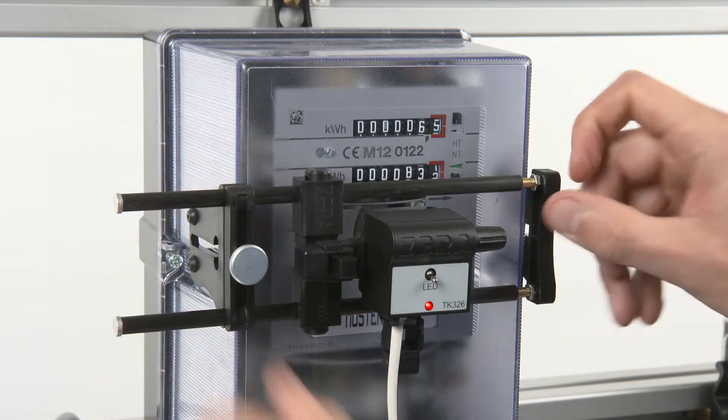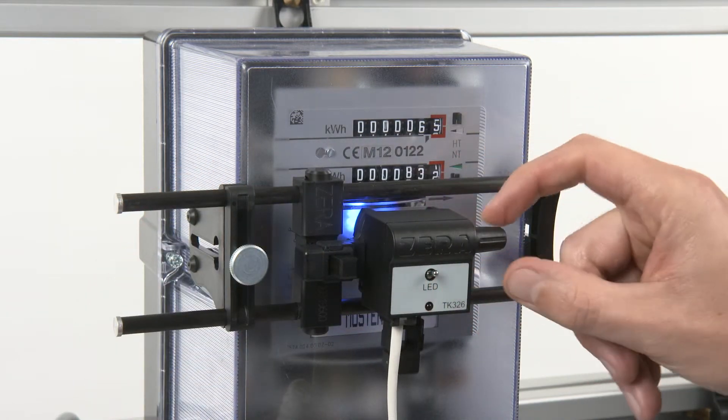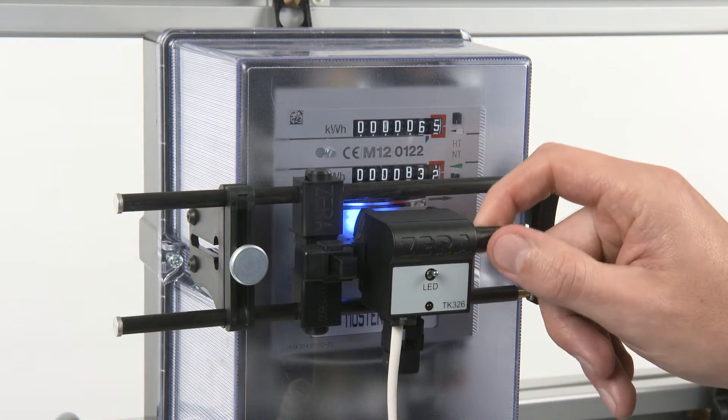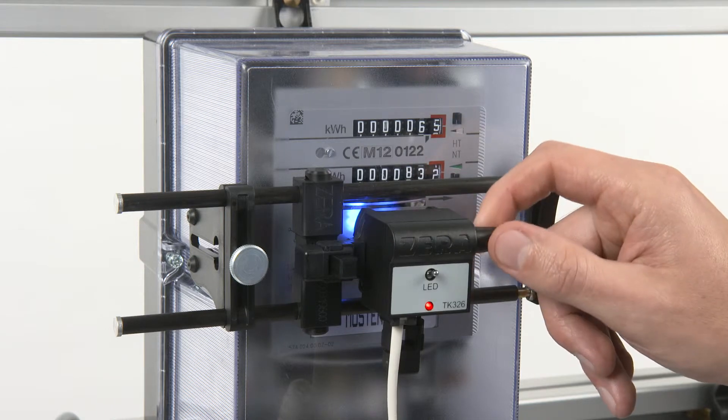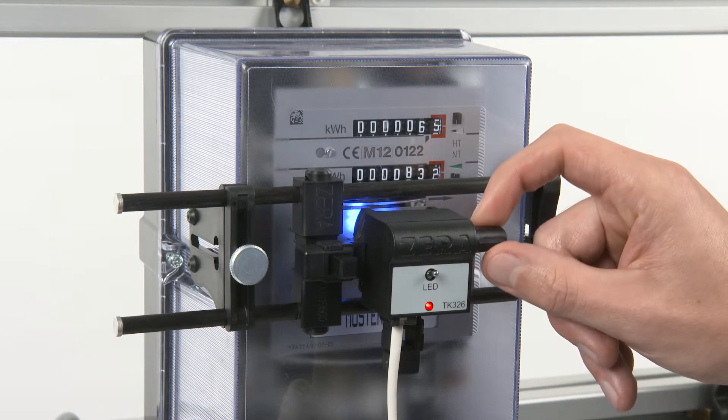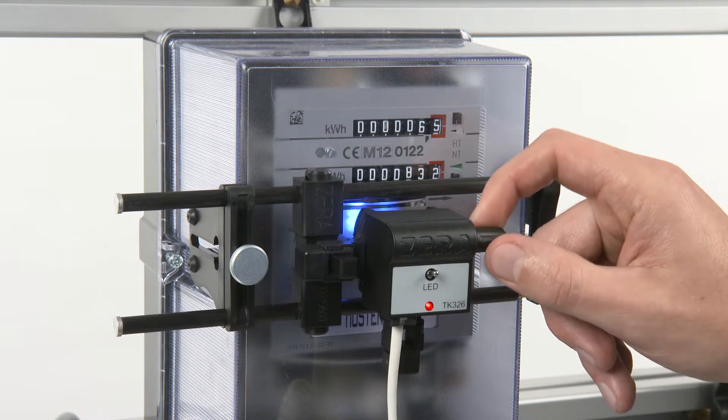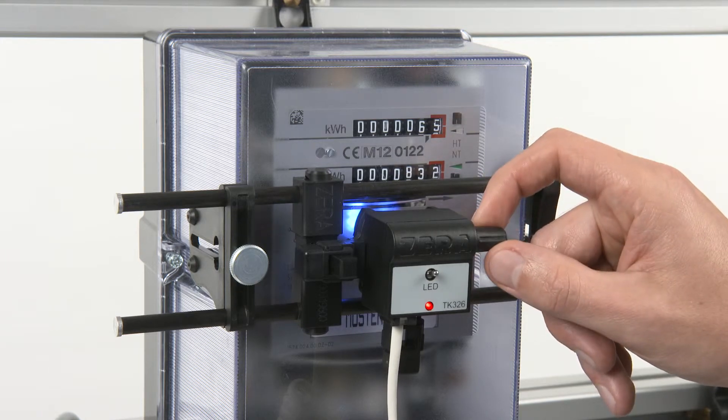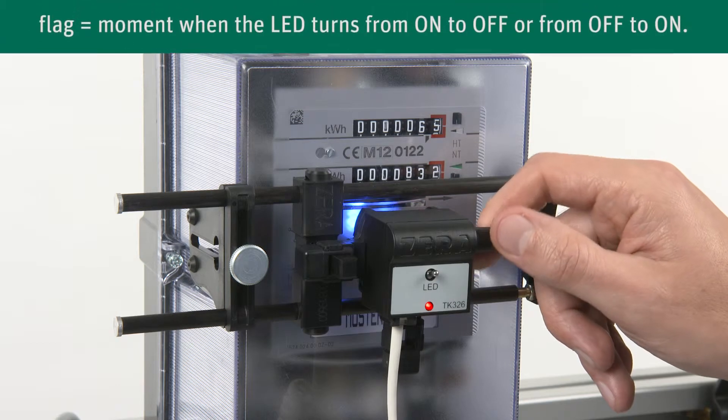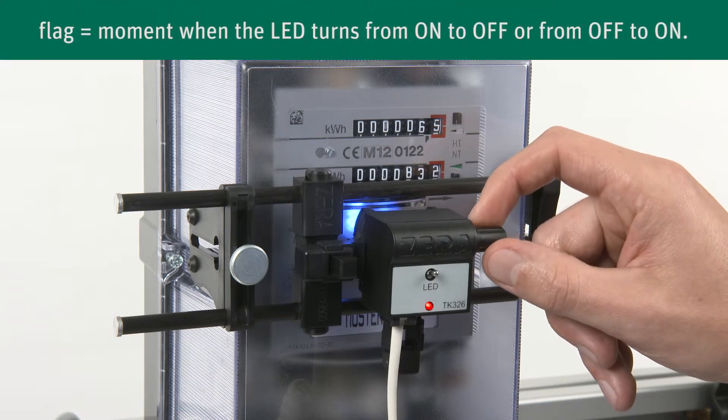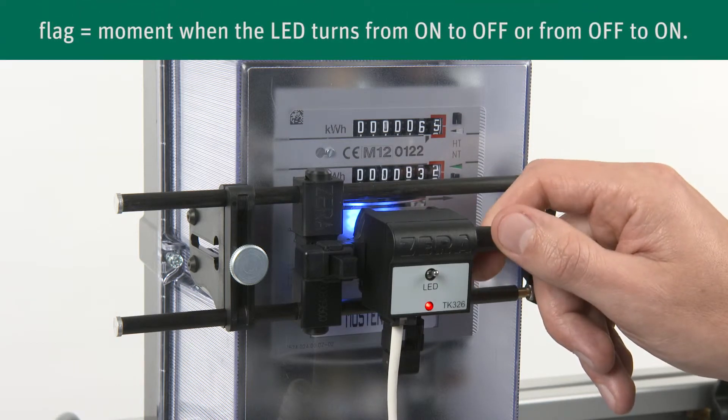Set the switch into the upper position. You can adjust the sensitivity of the scanning head by the potentiometer. As an indicator, use the red LED of the scanning head. First of all, try to find the flag of the scanning head LED. Then, adjust the potentiometer exactly while passing the rotor mark.